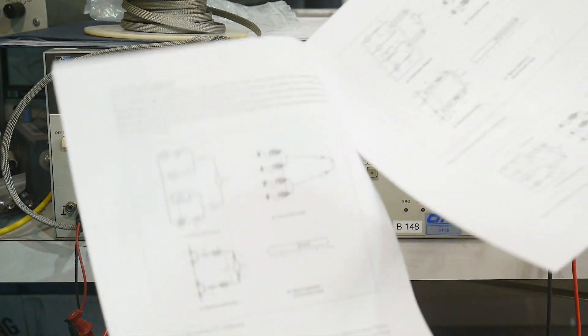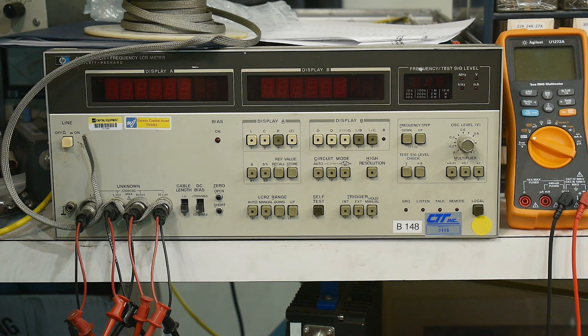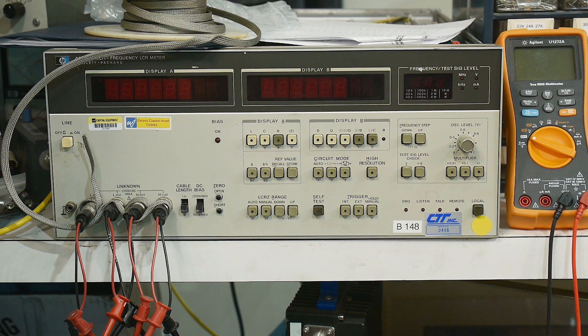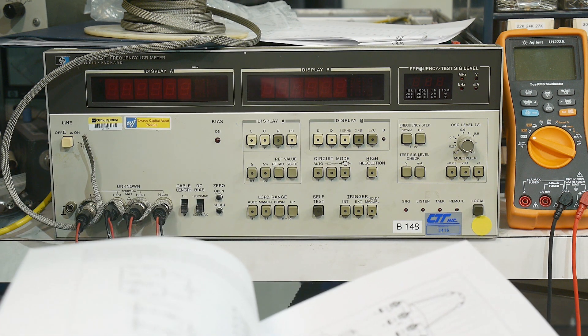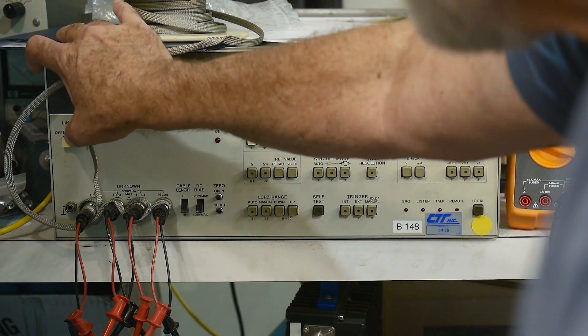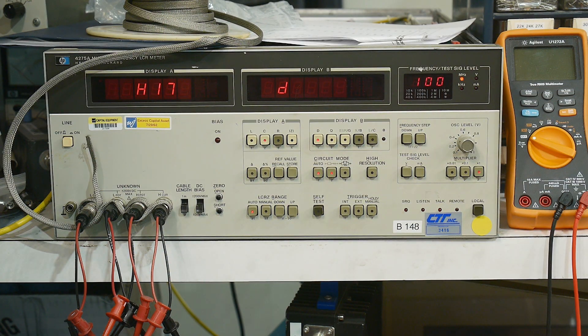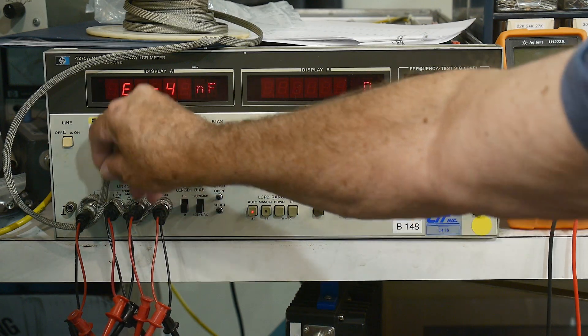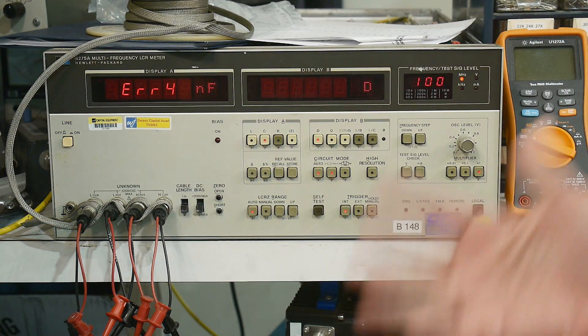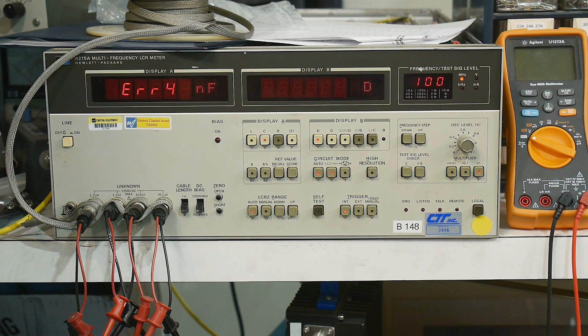What I will say is that these diagrams of how the cables are to be wired is very confusing. So I had first made the assumption that these BNC connectors were all referenced to ground. No, they're not. They're all floating. And so the simplest thing to do is I've taken some braid and I've just shorted out all of the outer BNC. So everything is all shorted together now and there actually is a ground connection over here too that you can use.